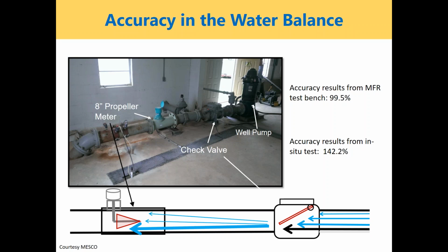Good deal, Will. The reason I asked is that's something we hear a lot: 'I'm testing my meters and my meters are checking out fine.' Many times that's just really assuring the 4 to 20 milliamp signal, but we're not doing a secondary or volumetric type test. Let me go ahead and pause again for questions.